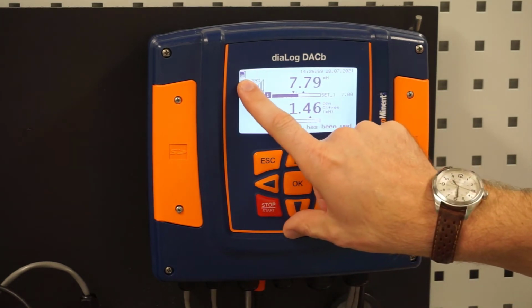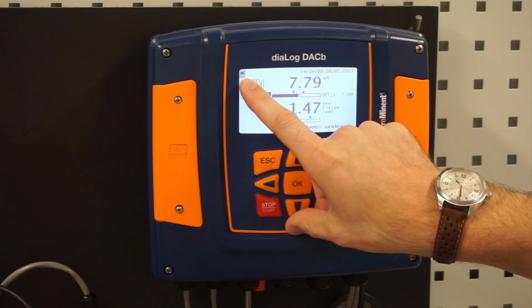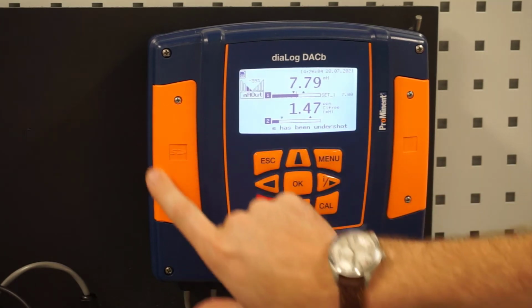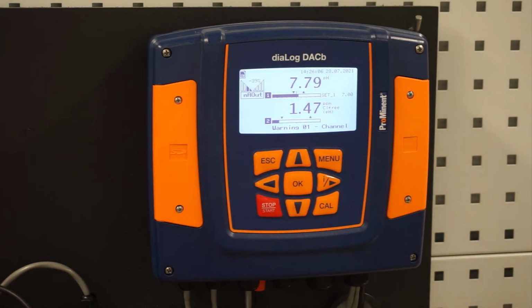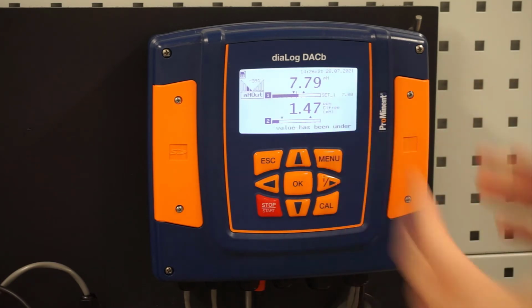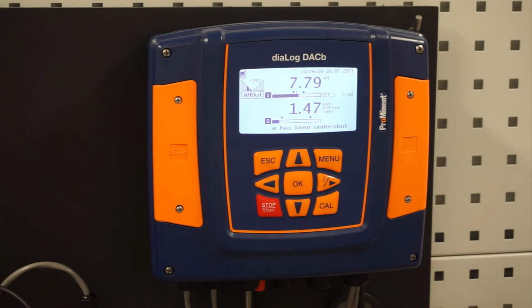You also see at the very top left there is a card and it says SD. That is an SD card that is underneath this flap. With that SD card I can log data. I'll walk you through the process to set that up. You can also save or load a configuration so that once I program this, I can save the configuration, put it on my computer, and then if somebody comes back here and messes with any of the program, I have a good starting point. I can also take that configuration to another controller that may have a very similar setup, and that gives me a very good starting point.